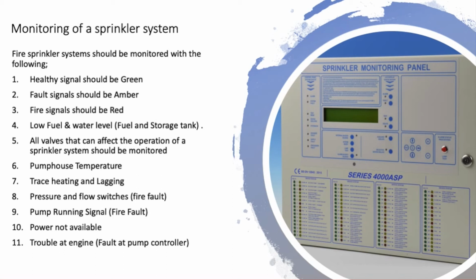All valves that can affect the operation of a sprinkler system should be monitored. Now they should be amber signals. Pump house temperature should be monitored also, amber. Trace heating and lagging, if there's any, that needs to be monitored. That should be amber. Pressure and flow switches, now that would be a fire fault because what it's doing is detecting flow of water. So if you get flow of water, a sprinkler head is activating instead of a fire. Pump running signal again, if the pump's running, it's a flow of water. You then get a fire fault.